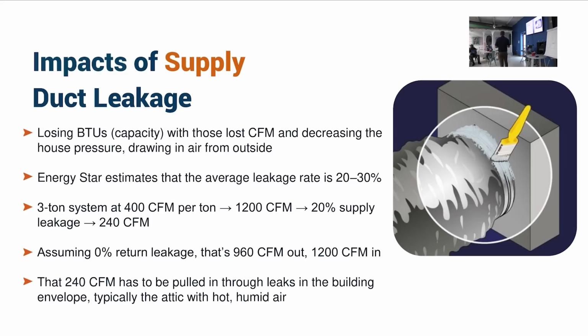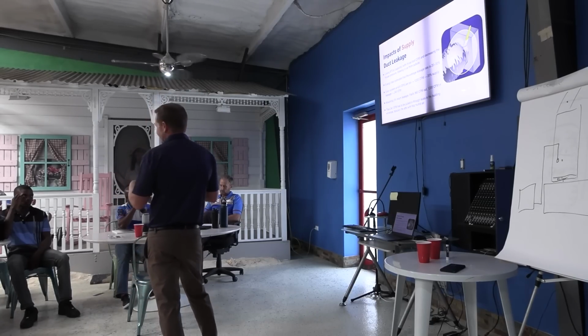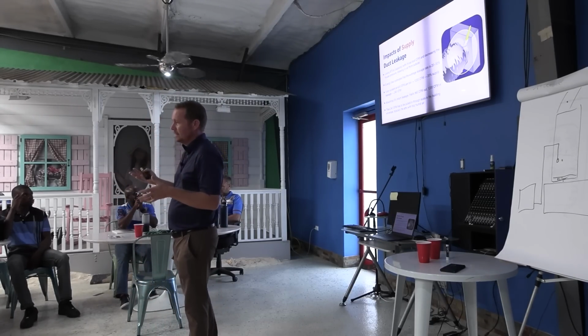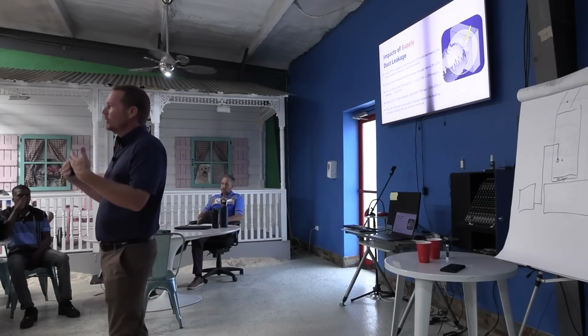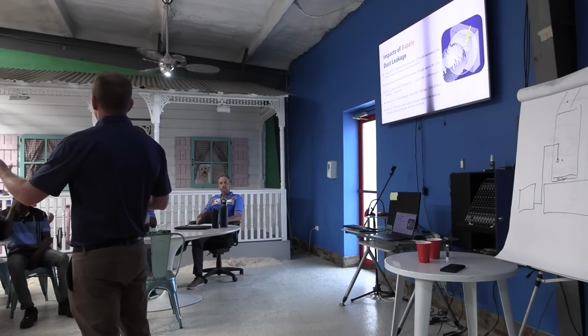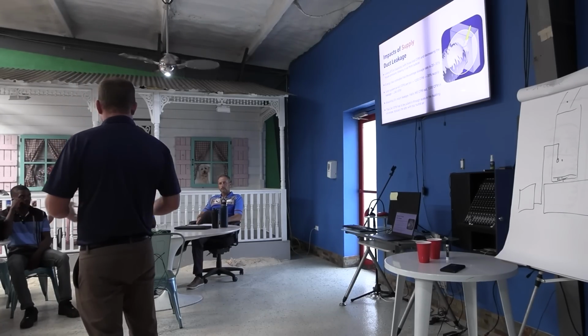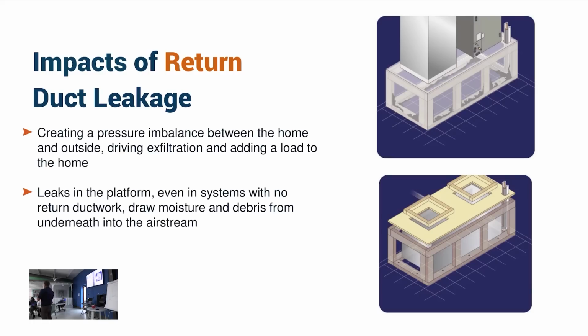So when ducts leak, it causes problems. On houses with a real moisture issue, once you've done the simpler things, really look at duct leakage. A lot of that can be visual inspection. I'm not the kind of guy who says you need to do a duct blaster on every install—I don't think that's necessary. Most of it is just, if you're doing an install, especially where you know there's already a moisture problem, or on a sales call where you can see it's part of it, really make that duct side of things part of it.